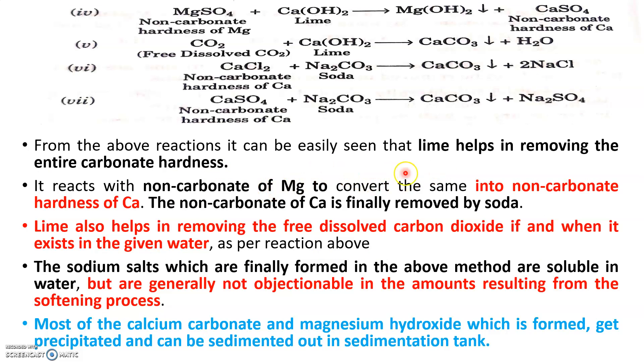When you add lime, it removes entirely the carbonate hardness itself. The reactions with non-carbonate of magnesium convert it into non-carbonate of calcium, and this non-carbonate of calcium can then be removed by soda itself, as you can see with respect to the above reactions.